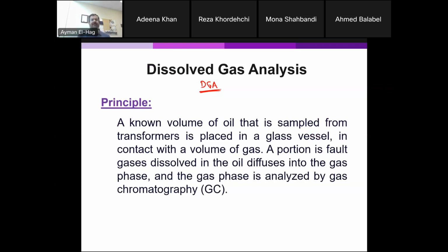Now, there is a difference between the DGA and the other tests we mentioned. The other tests don't necessarily reflect the existence of a fault. They might, but the previous tests are basically a measure of the aging process that happened to the oil, the overall aging of the transformer, getting older and older. So these numbers would start to either increase or decrease, depending on what type of parameter we are talking about. But the dissolved gas analysis is an indication of a fault happening inside the transformer. The transformer could be a new transformer, the oil maybe not aged oil. It's not related to the age of the oil, but to the existence of a certain fault in the transformer.